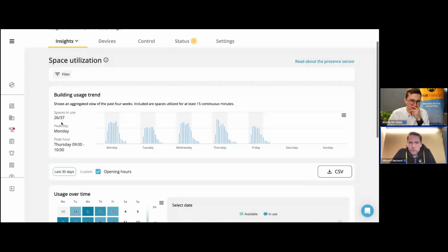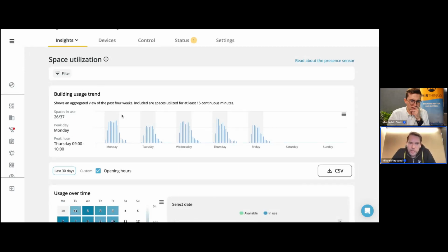So in this case, you can look at this building usage trend, which aggregates the past 4 weeks in terms of presence in your building. And you see here that the gray area indicates opening hours, and the start here is 7 a.m., but there are rarely a lot of people in our part of the building, at least, until maybe 8 or 9 a.m., not p.m., sorry. So this is an indication that, assuming ventilation in this building starts at 7 a.m., that might be a bit too early. It could probably start at 8 a.m., for example.